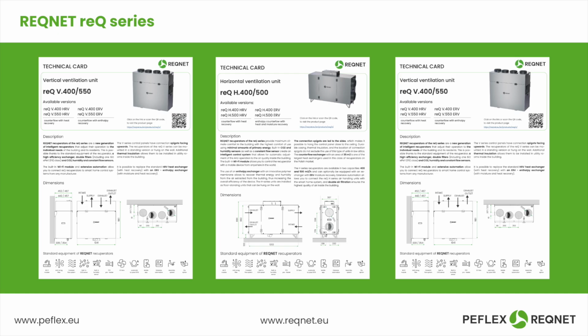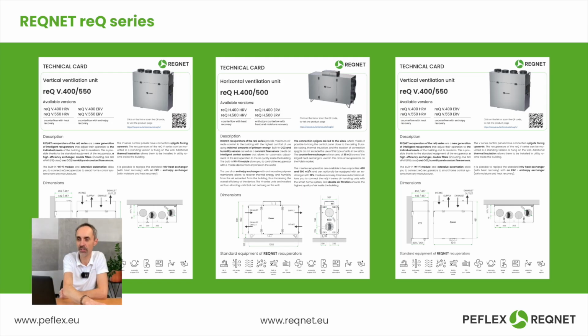When it comes to the reQ series recuperators, we have 3 models: the V recuperator, the H recuperator, and the F recuperator. The V recuperator, which has vertical outlets facing upwards, comes in capacities of 400 and 500 cubic meters, and we also have the option to choose the type of heat exchanger. Will it be a standard HRV heat exchanger, or will it be an enthalpy ERV heat exchanger? It's the same situation with the H recuperator, which comes in 400 and 500 cubic meter capacities, and also offers both the standard HRV heat exchanger and the enthalpy ERV heat exchanger.